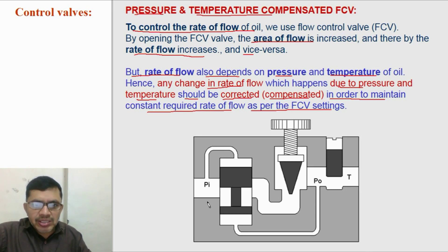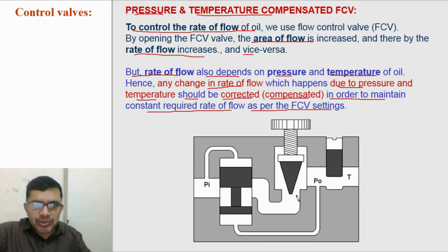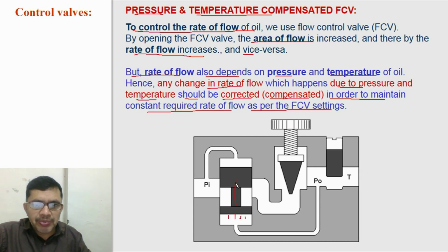For which, we use this arrangement for pressure compensation and this arrangement for temperature compensation. If pressure increases at the outlet of this flow control valve, then the rate of flow will reduce. To compensate this, we have a mechanism here. Due to this pressure, it acts in the upward direction on this spool and the spool will shift upward, allowing the passage for oil flow to increase and allowing more oil to flow through the flow control valve.